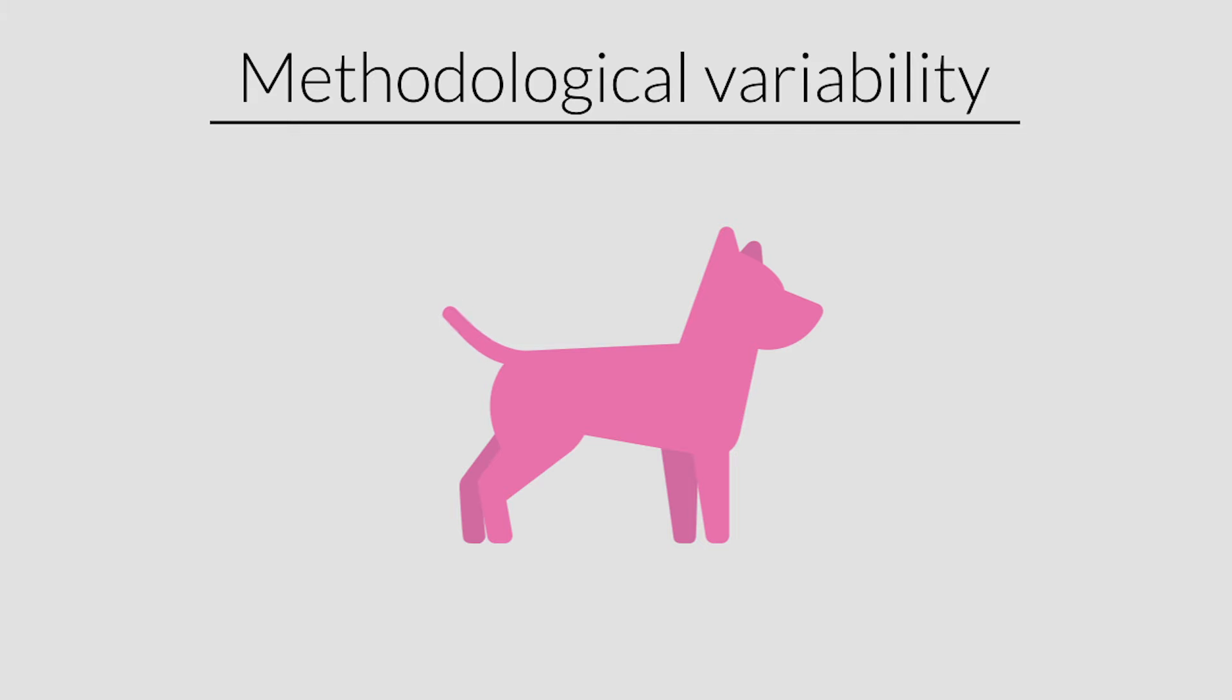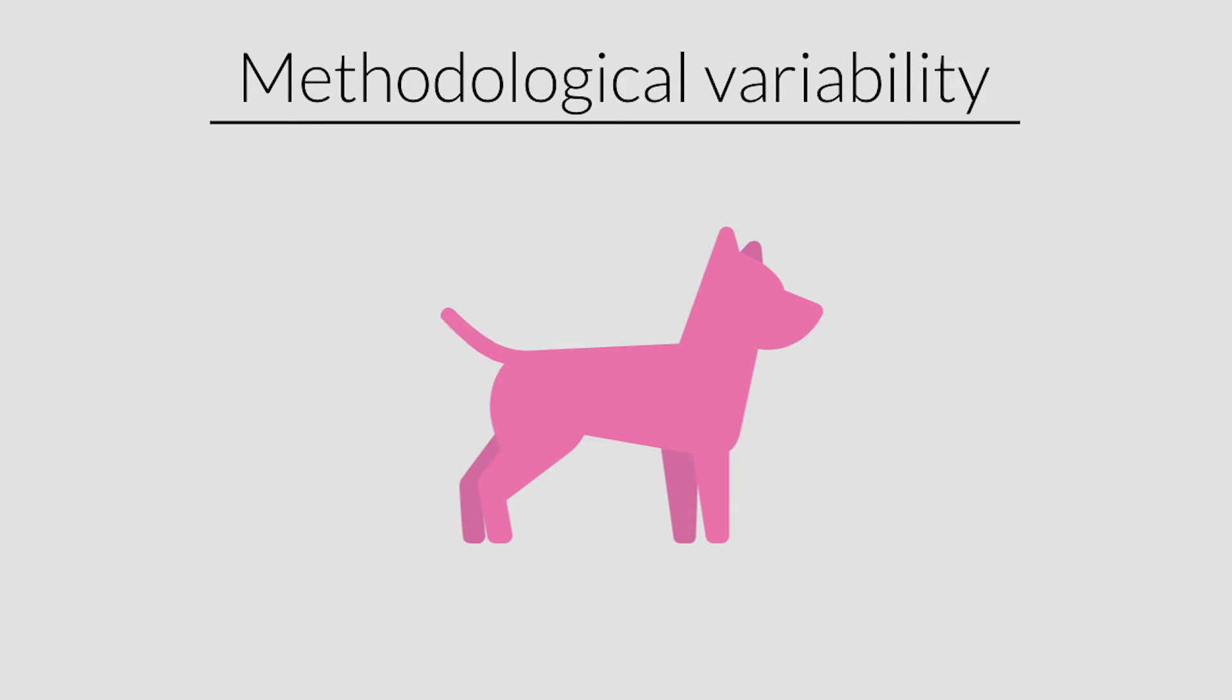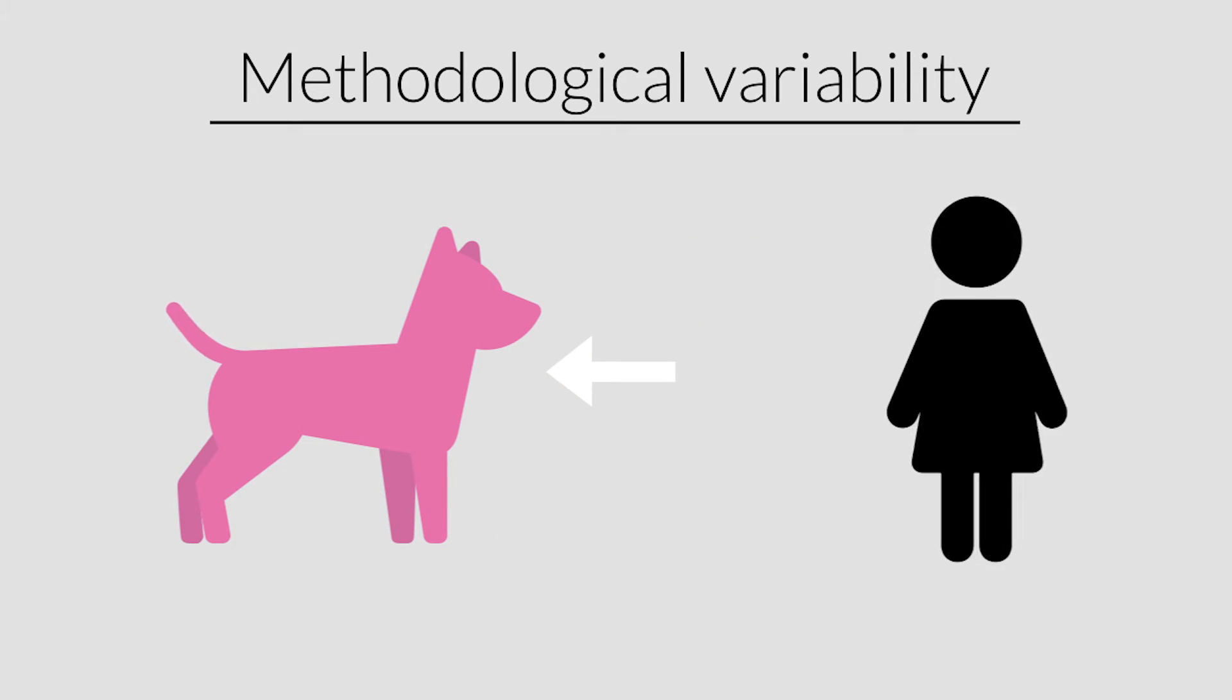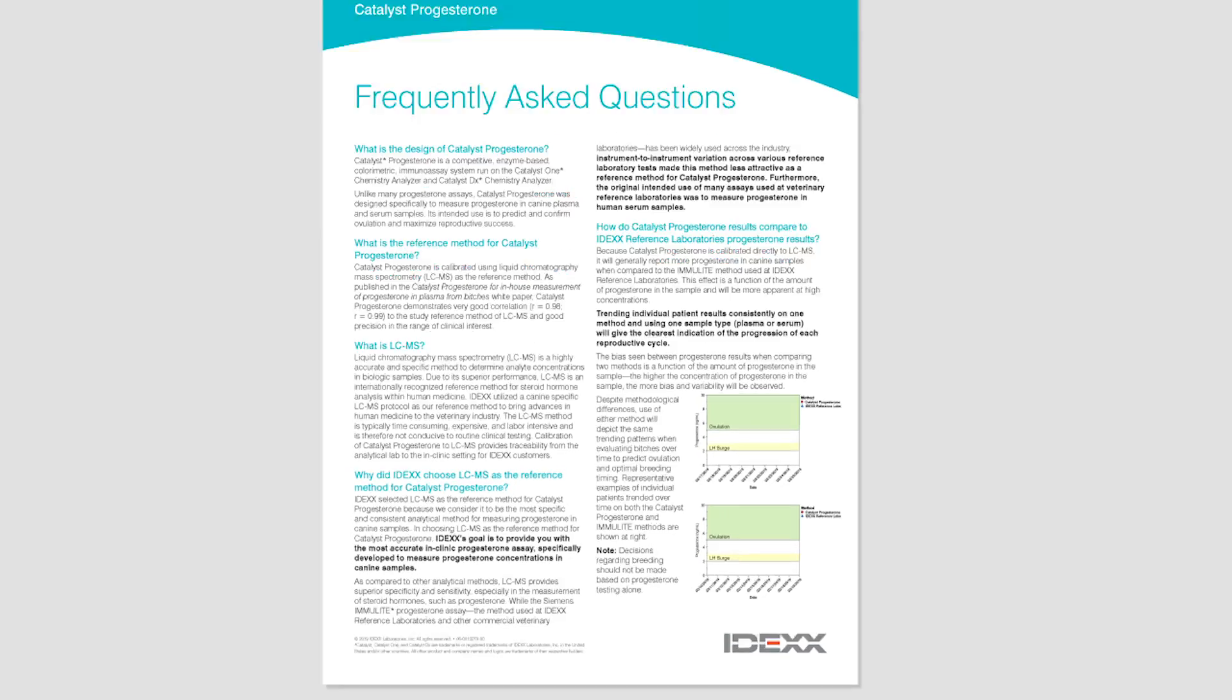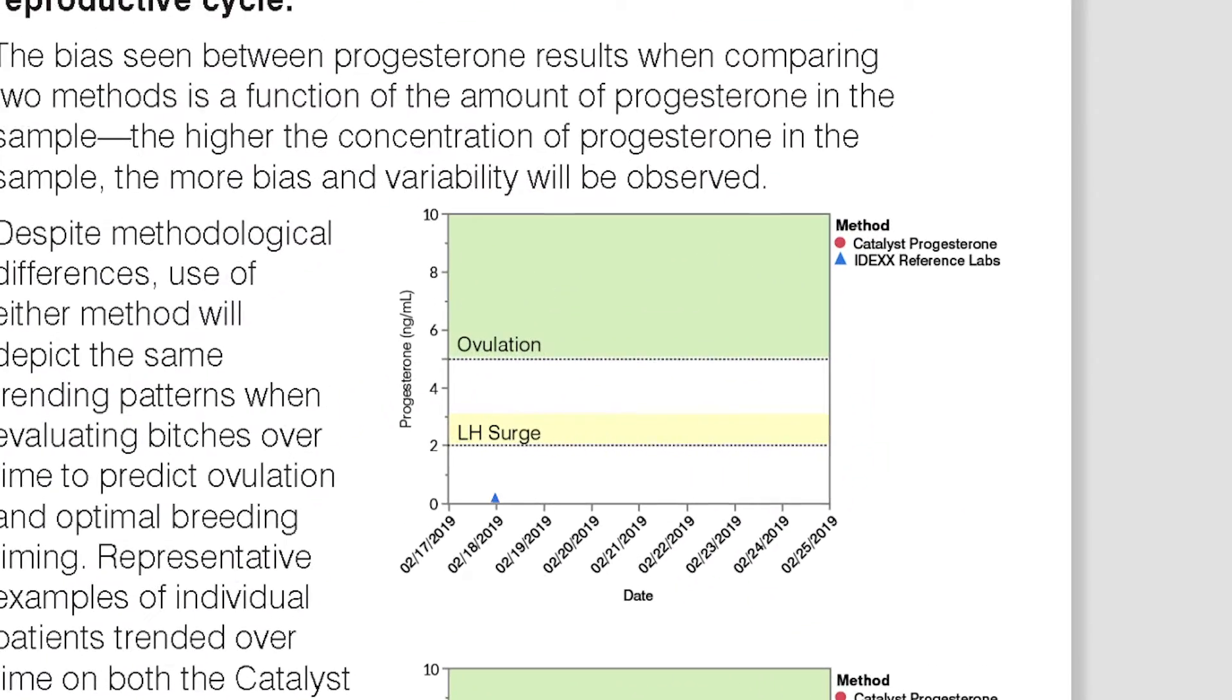Although widely used and accepted, many progesterone assays used in the veterinary industry were originally developed for the human market. Because Catalyst Progesterone is calibrated directly to the highly accurate and specific LC-MS method, it will generally report more progesterone when compared to the IMMULITE method used at IDEXX reference laboratories.